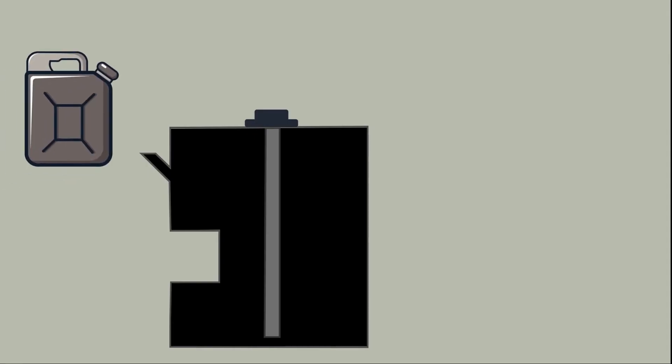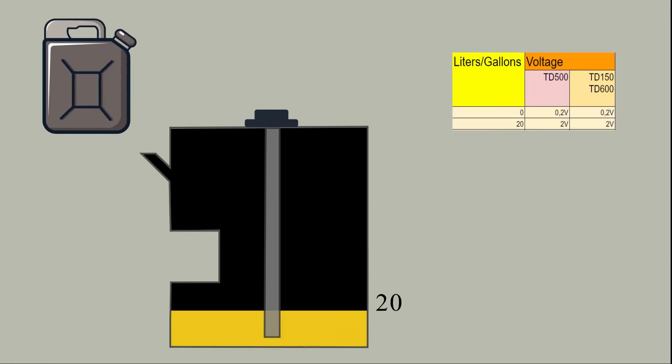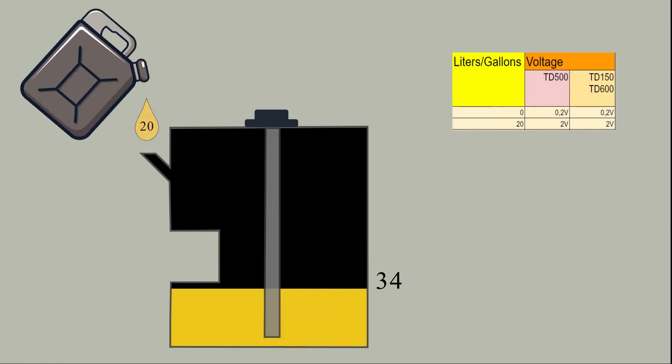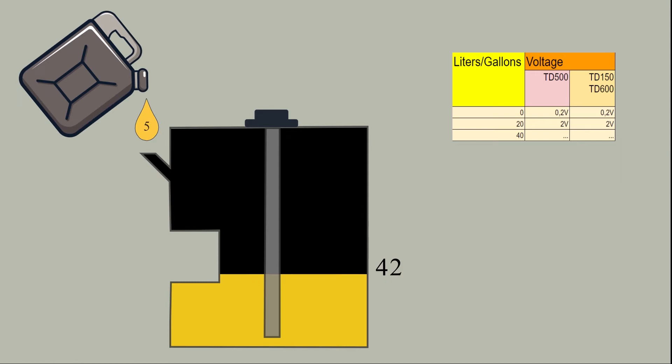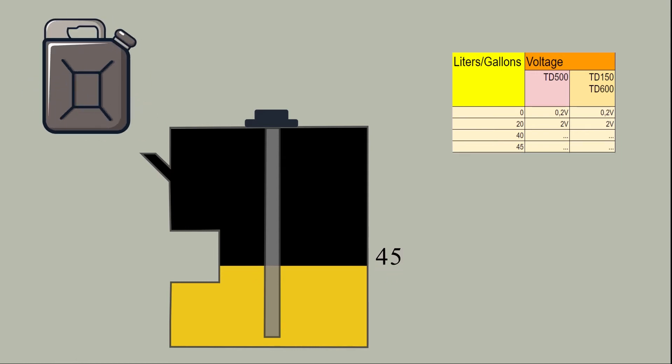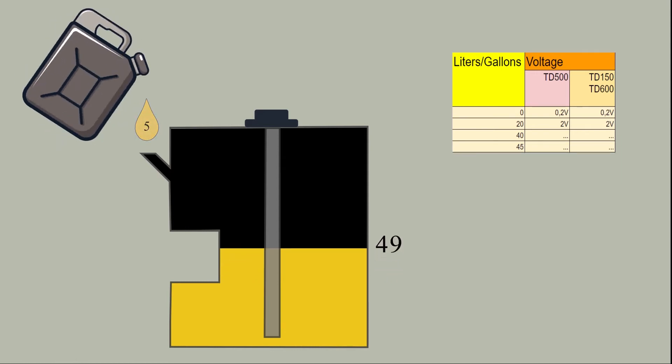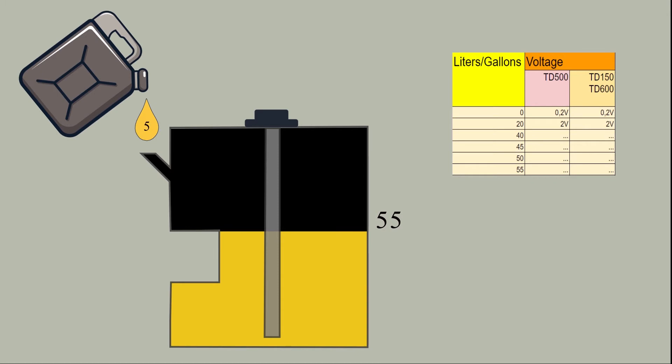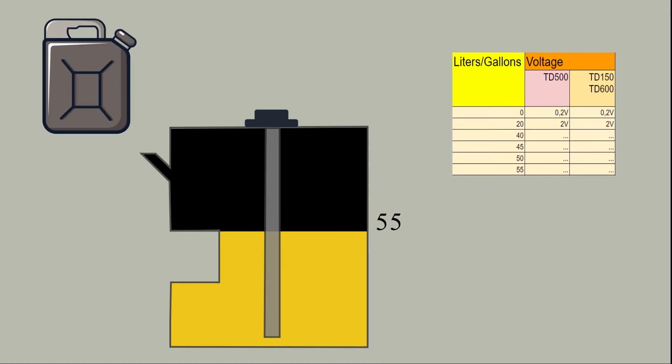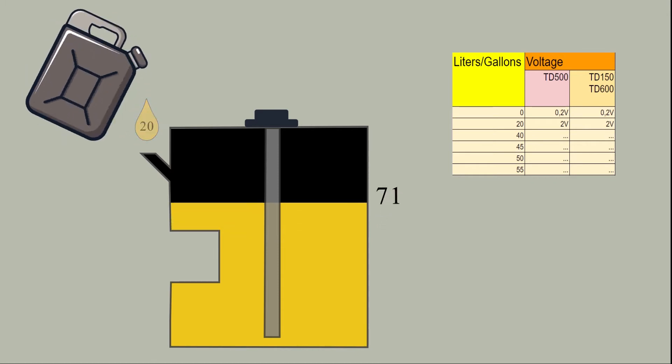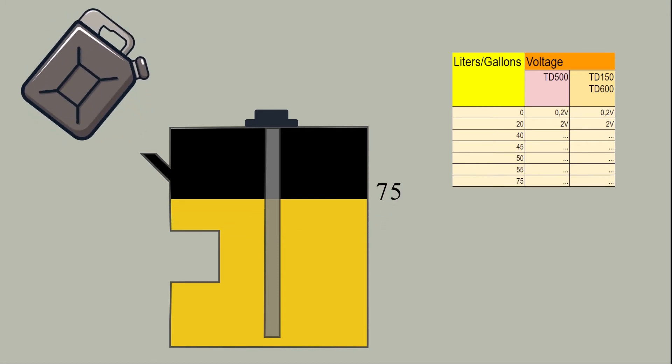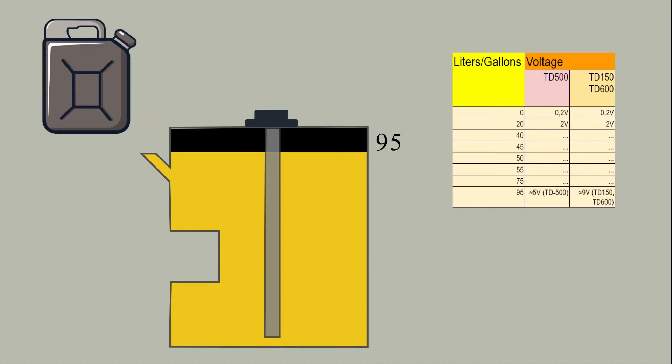After calibrating the sensor, you need to pour at least 10 or better 20 portions of fuel of equal volume into the tank and put down the level readings in volts against the liters or gallons in the tank calibration table. Based on this table, your monitoring platform will be able to convert the level readings of the sensor into liters or gallons. The more portions you add, the more precise will be the conversion.